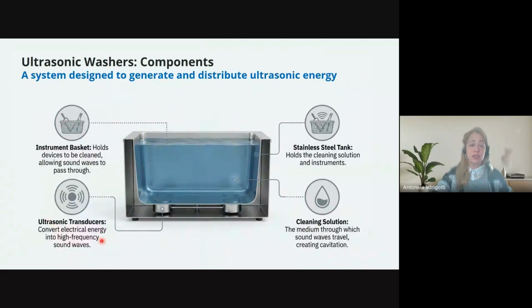The most important part of the ultrasonic washer are actually the transducers that normally, in the conventional configuration of the oldest versions of ultrasonic washers, are below the tank. Of course, with the advancement of different technologies, nowadays there are some manufacturers that also offer transducers on the walls of the tank, and especially those that offer a multi-layer or multi-level configuration. But generally, transducers are at the bottom of the tank, and they convert electrical energy into vibration of the water of the washing solution in the ultrasonic range. And this is why they are called ultrasonic washers, okay?